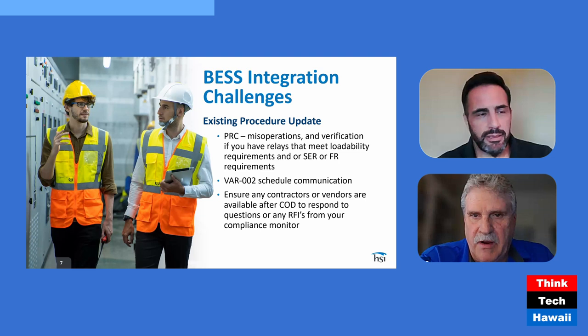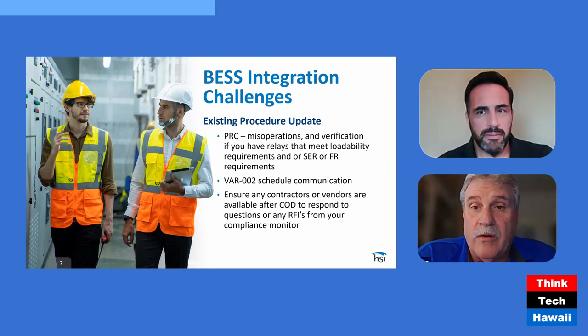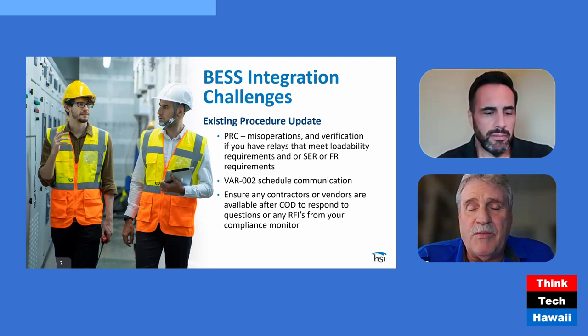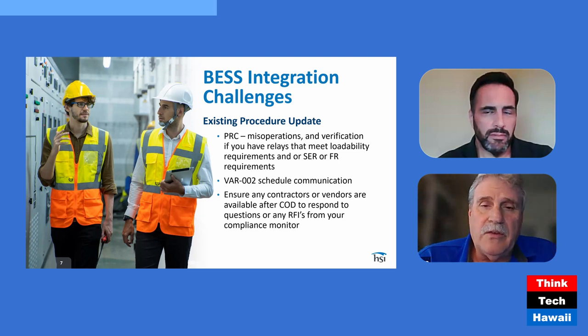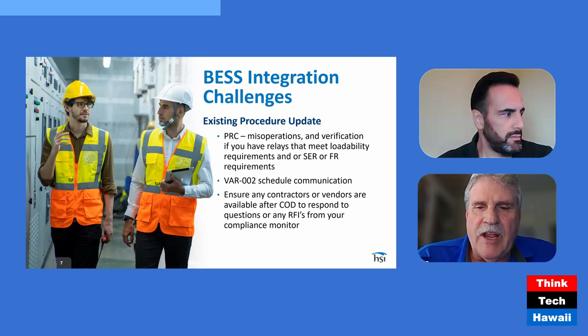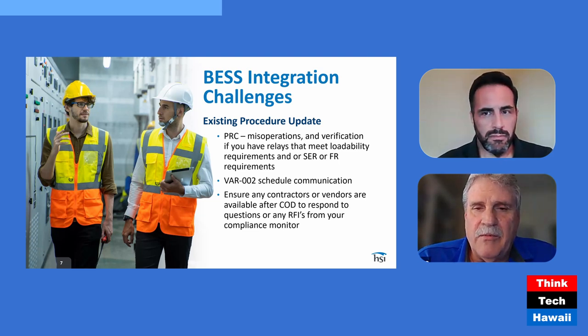As far as the PRC and the misoperations, that's reported quarterly now if you have an operation of a protection system component. So obviously you're going to have more of those. You're going to have components that protect your battery storage facility just like it was a generator, so that's going to add to that. It doesn't happen a lot, but when it does, you need to make sure the operation was correct, that it wasn't a misoperation, and that the relays didn't respond to something that wasn't actually happening.